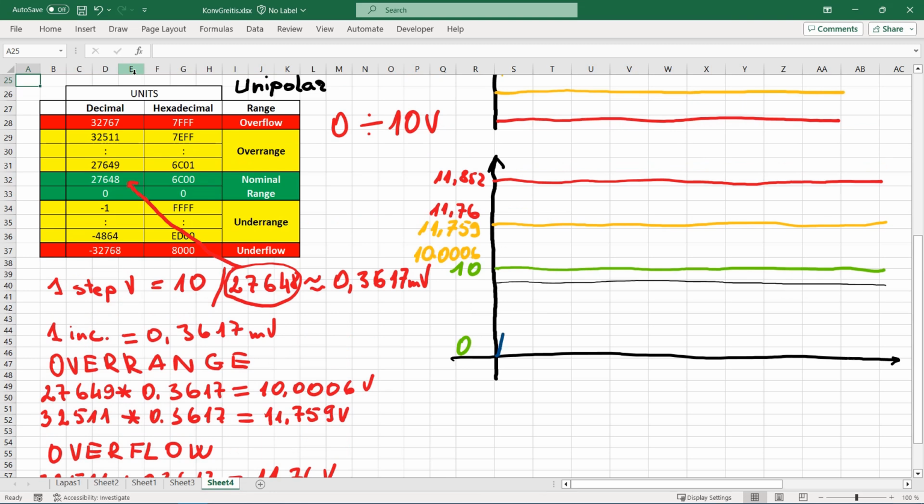In first scenario, our signal exceeds 10 volts a little bit. Then gets back to a set point of 9.5 volts. No error is reported, as signal did not reach 11.76 volts. In second scenario, we can see that signal did reach about 11.8 volts, so overflow error is stated.